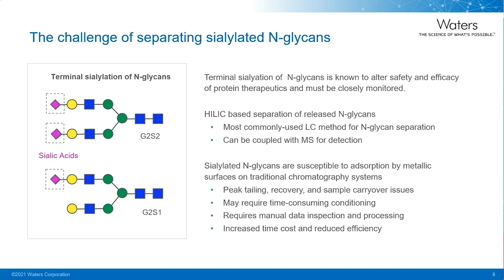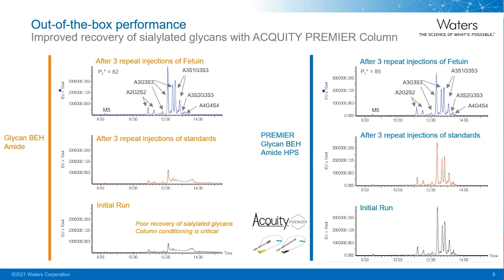Here's an example of how a Waters Premier column can improve separation of sialylated glycans. On the left figure, the sample is a sialylated glycan standard separated on a conventional glycan BEH Amide column. Both the initial injection and the injection after conditioning have shown very poor recoveries. It only achieved better recovery after additional conditioning rounds. On the figure to the right, the same sample was separated on a Premier column instead. The improvement here is very clear: even without any conditioning rounds, the separation has achieved pretty optimal recovery. Together, this shows the out-of-box performance of Premier columns. It is expected to perform right from the beginning, consistently, regardless of cleaning and conditioning status.